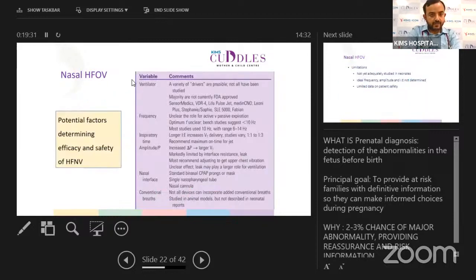So the factors that affect ventilation and oxygenation in nasal HFOV are again the type of ventilator and the mechanism of ventilation that it uses. The frequency, although the optimum frequency that has to be set is unclear, the exponents who use nasal HFOV routinely set frequency between 6 to 10 hertz. The third parameter is the inspiratory time, that is the IE ratio. IE ratios in general vary between 1:1 to 1:3. The most commonly used IE ratio is 1:2. The fourth parameter is the amplitude or the change in pressure. Change in pressure is in general kept as twice of the mean airway pressure that is routinely used.